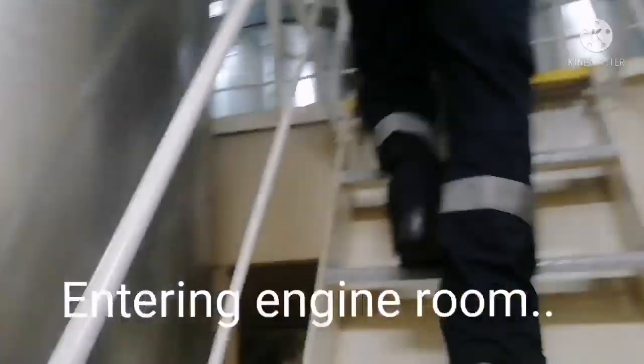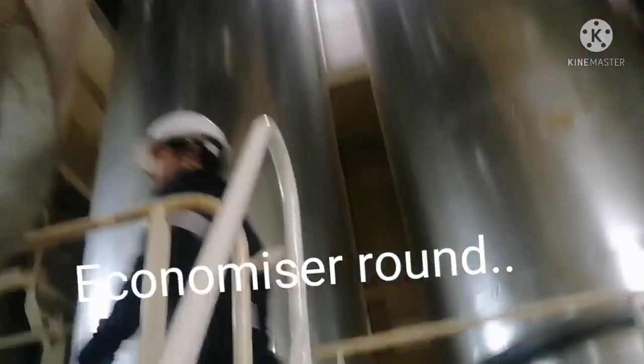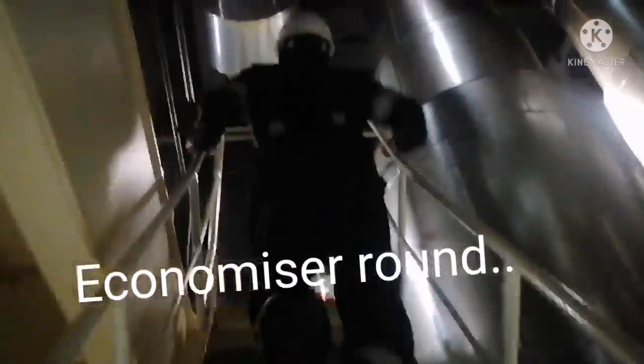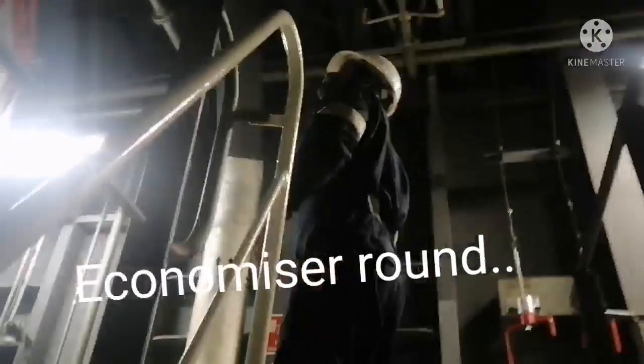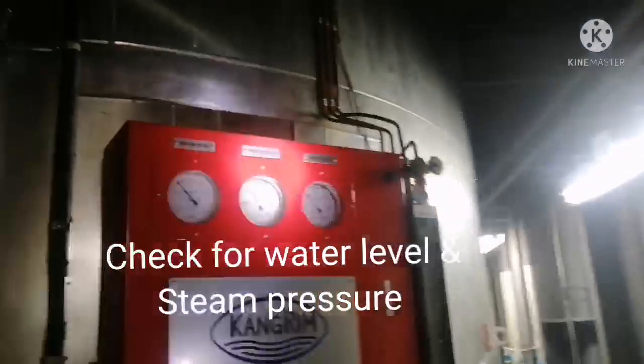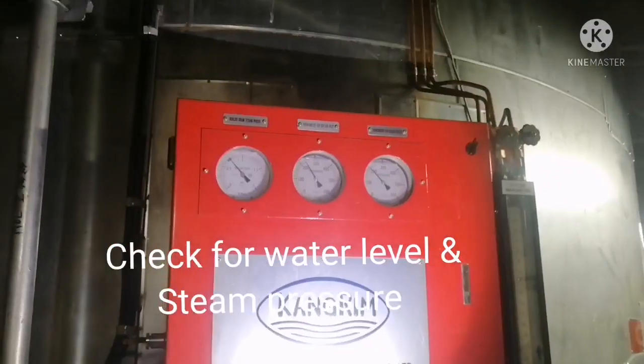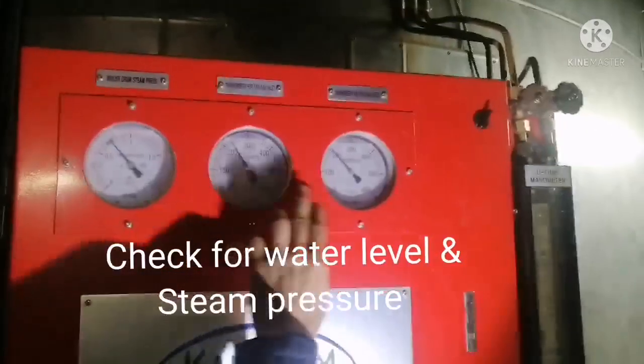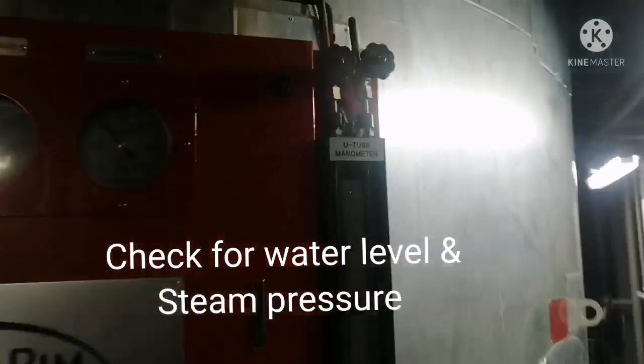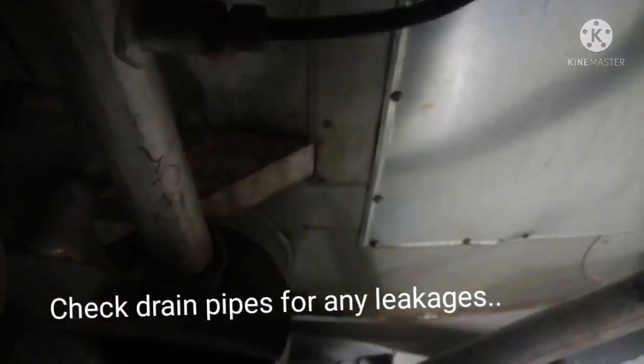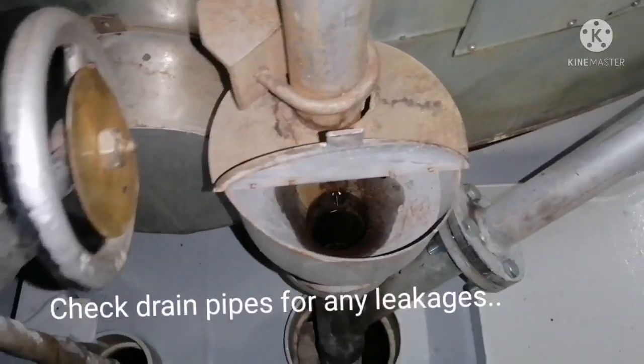Now I am entering the engine room. So, the engine room economizer platform I am in. All you have to do is check the economizer visually from outside, and check the water level and steam pressure in the economizer. You can verify with the gauge, and you can see the water level in the water level gauge glass. And you have to check the drain, whether there is any leakage in the drain pipes, so that you can find from where the leak is coming. And you just have a visual round around the economizer.